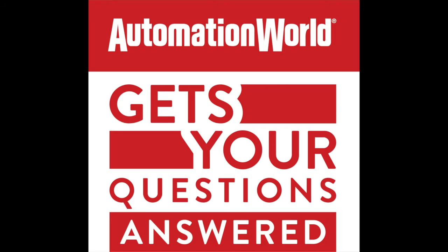Hey, Dave, thanks. That's a great question. Certainly some of the most common solutions would be either fans or air conditioners, but it's important to understand that these are used in total opposite types of environments. So fans, for example, do not cool air. Doesn't matter how big they are, how fast they're running, how many of them you put on an application, they only move the air. And it's going to be the same temperature in the front of the fan as it is on the back side. Actually, if you had some very sensitive kinds of measuring equipment, you would find out that you're actually warming the air when you do that.